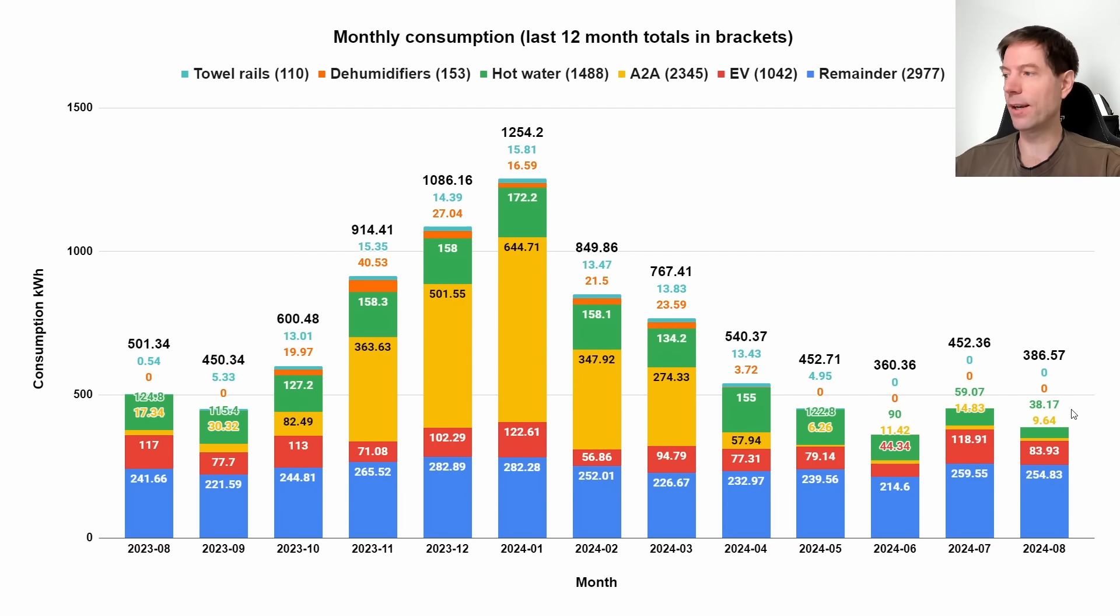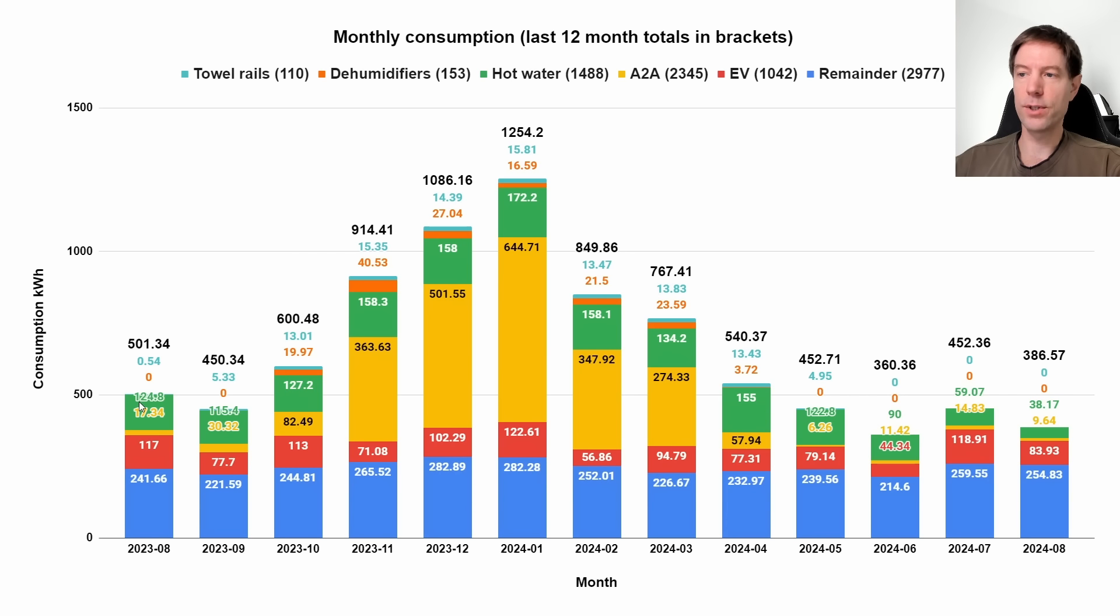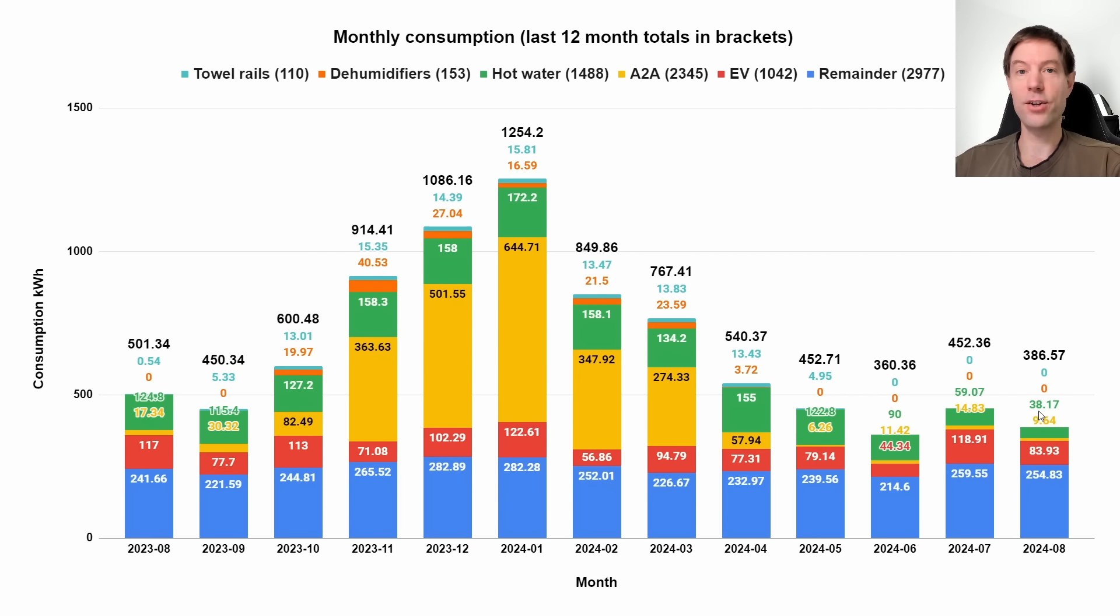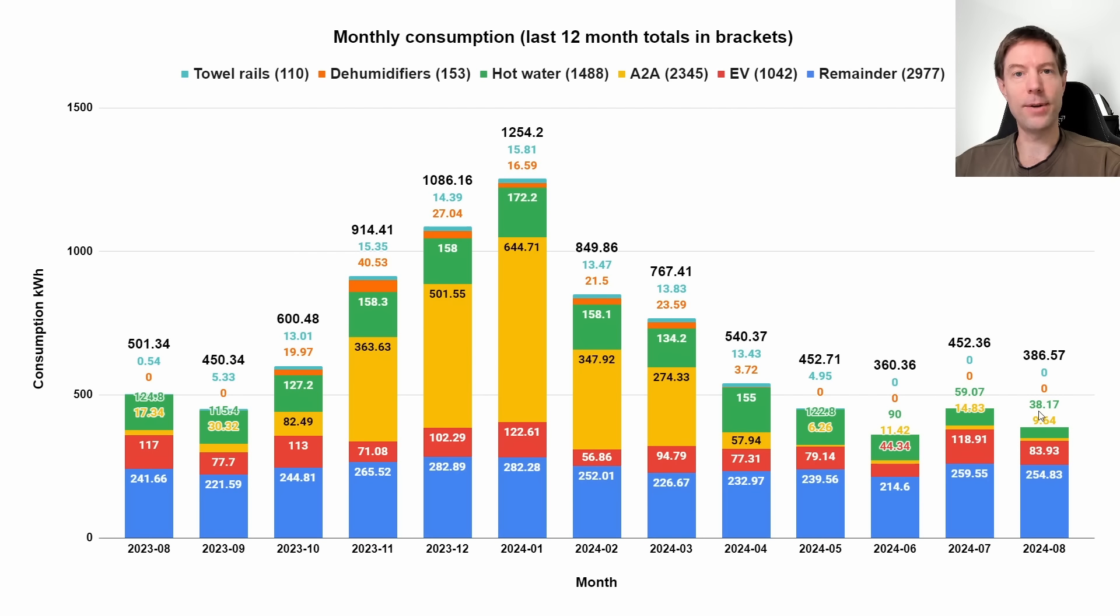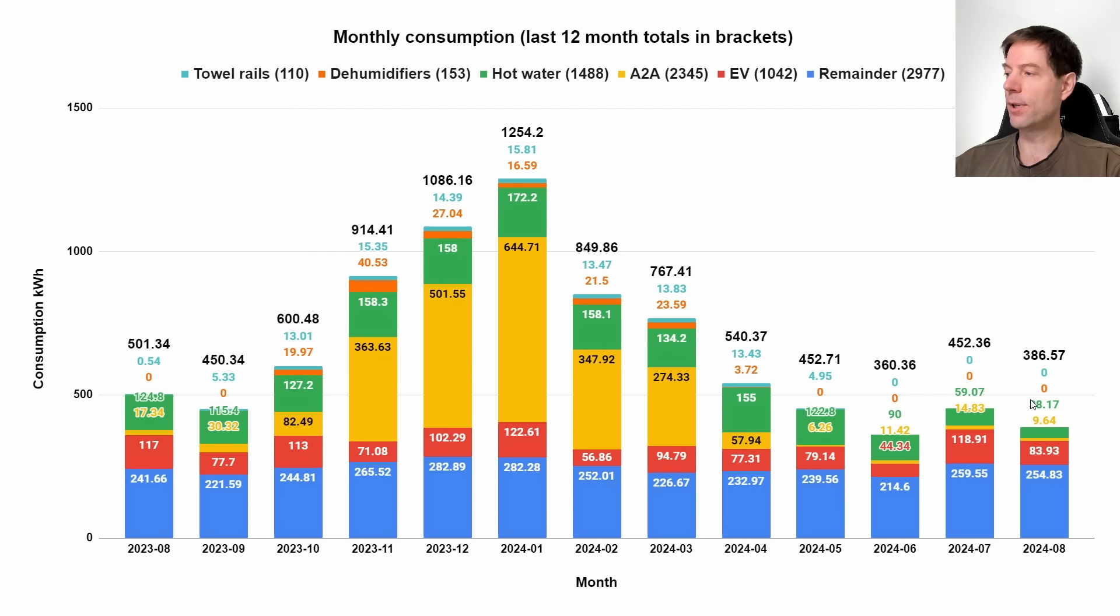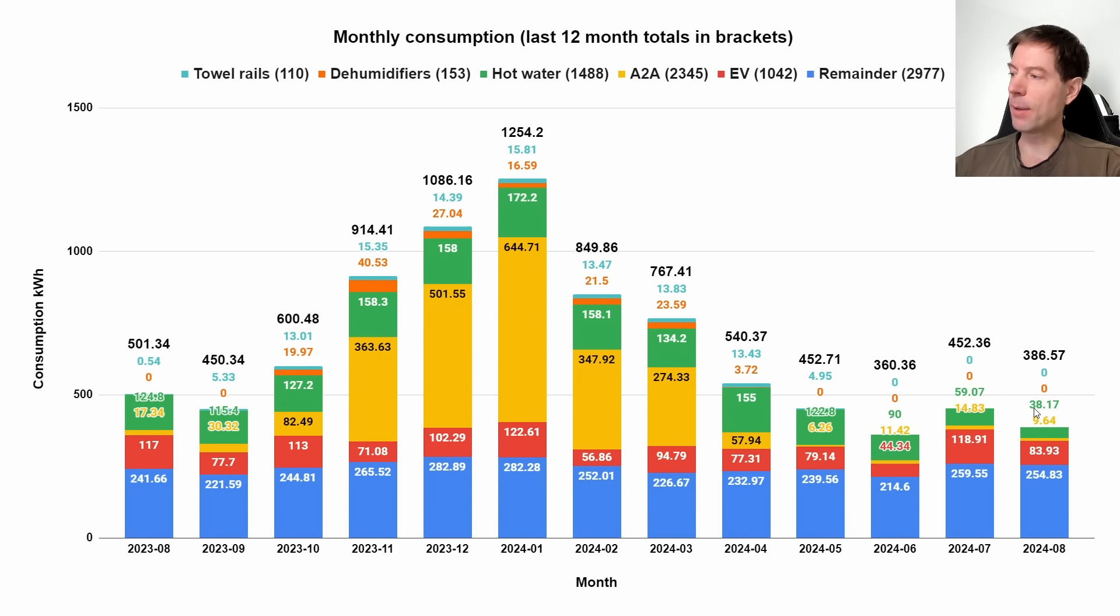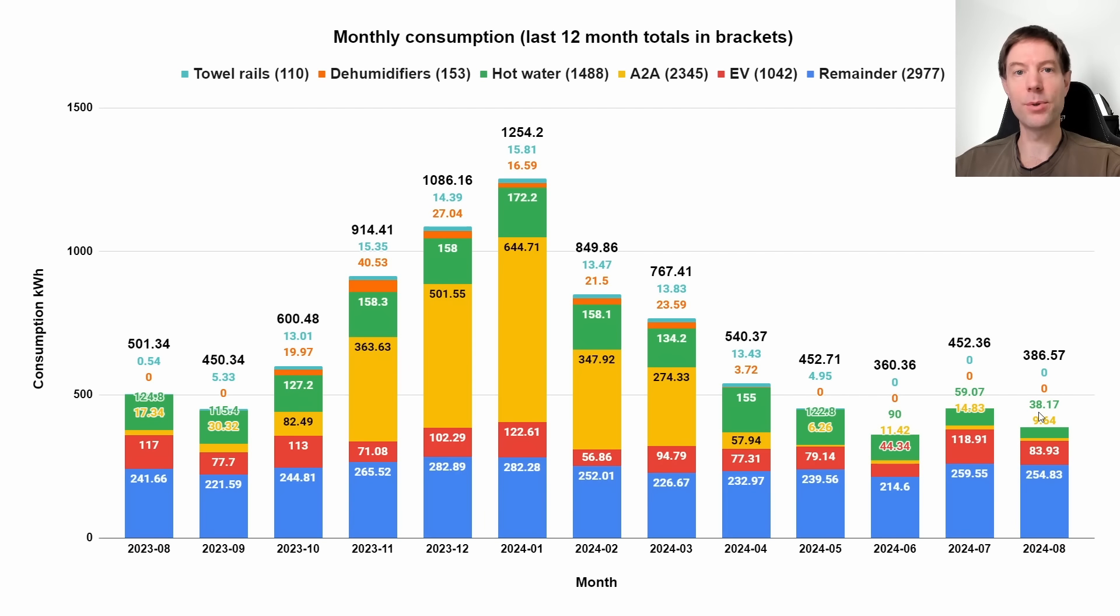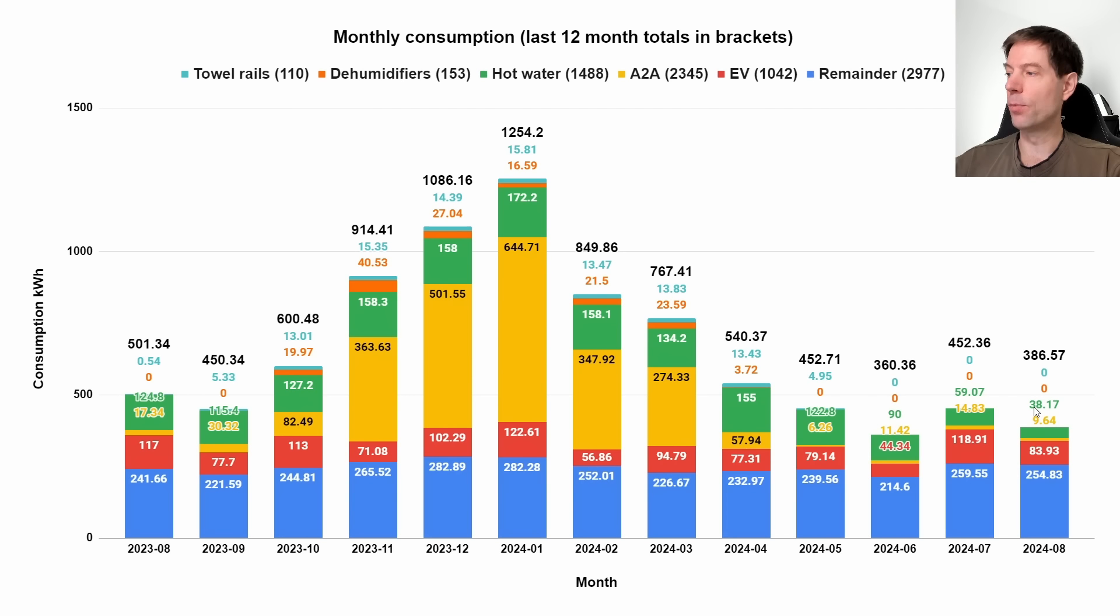The most interesting thing for this month is the hot water, which you can see is only 38.17 kilowatt hours, compared to last year. This is August from 2023, our hot water usage was 125 kilowatt hours, so we're down to less than a third of what we were using this time last year. That's entirely down to the fact that we're now using the Mixergy IHP cylinder, this integrated heat pump cylinder that we got installed about a month and a half ago now. It's been working fantastically, it's done exactly what we intended. The energy consumption for heating our hot water is slashed right down. This is about the level I would expect for the next few months. As we go into winter, it's probably going to creep up a little bit. I'm expecting maybe for it to hit closer to 50, maybe a bit more.